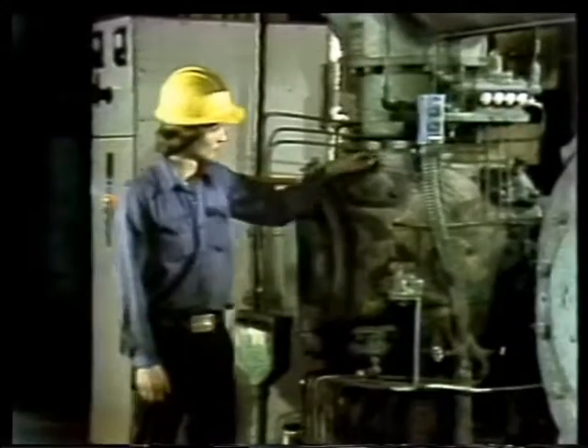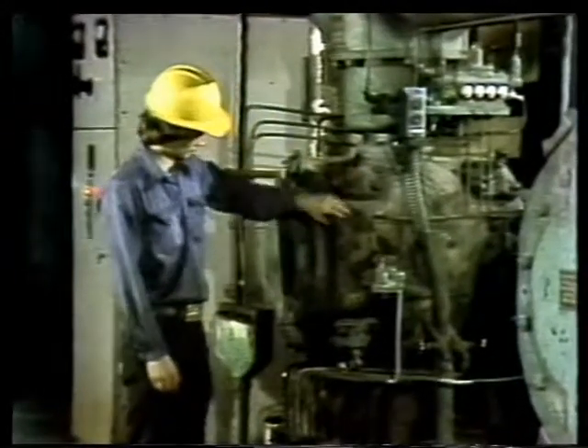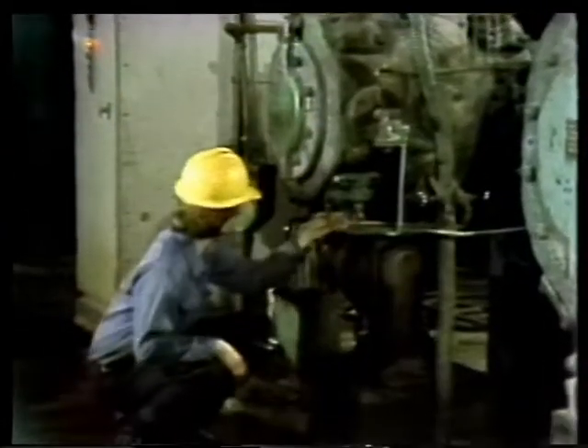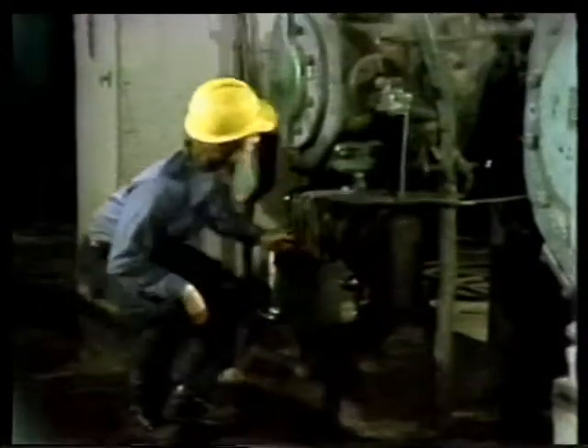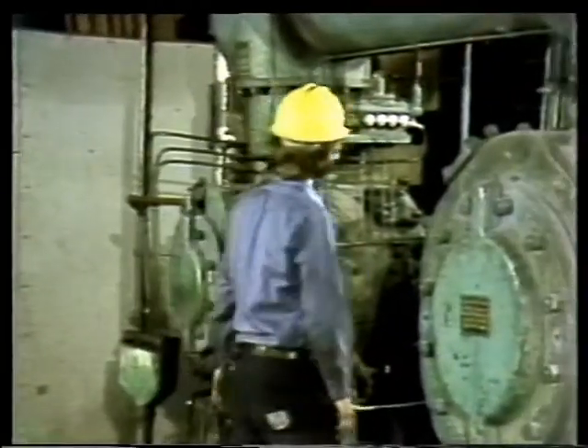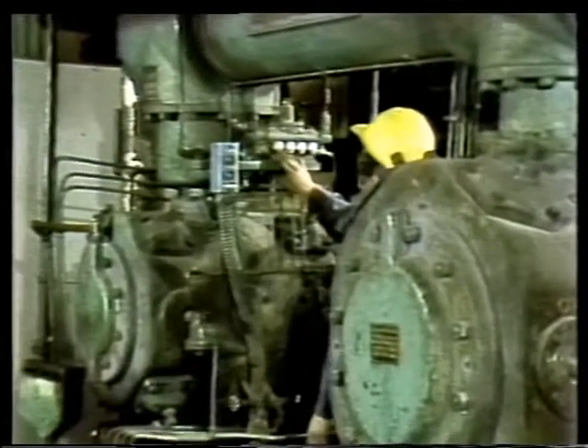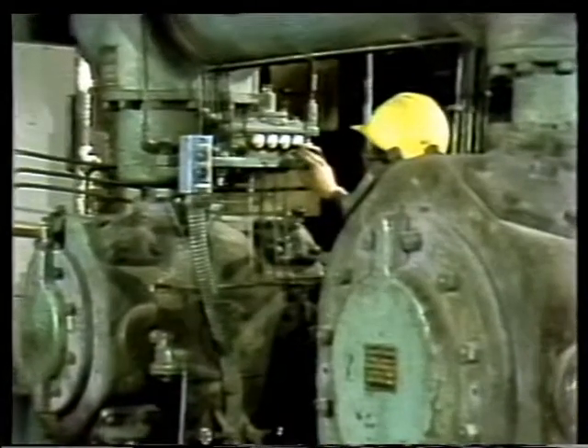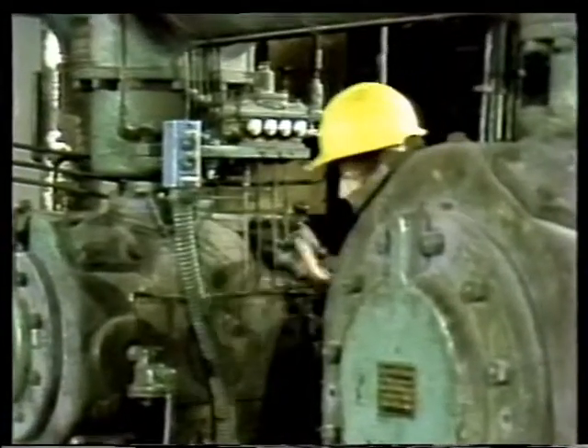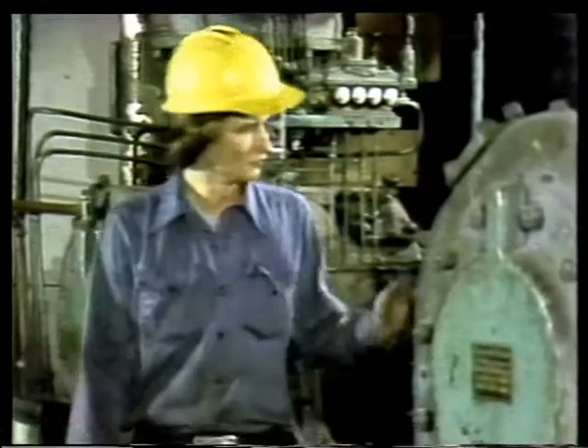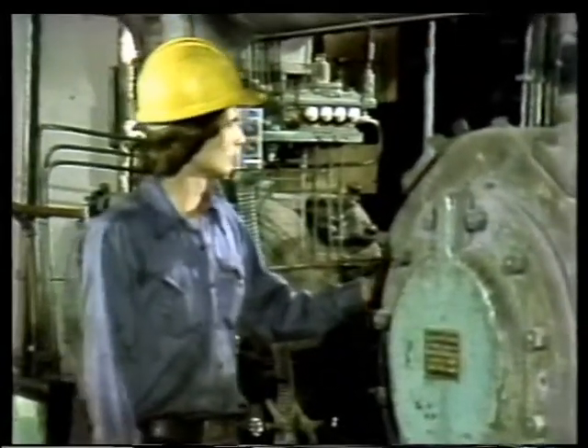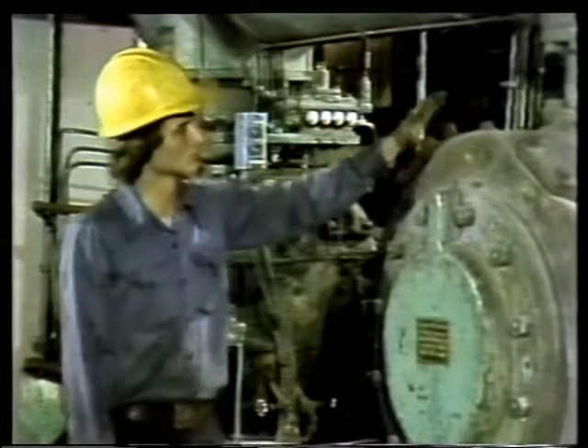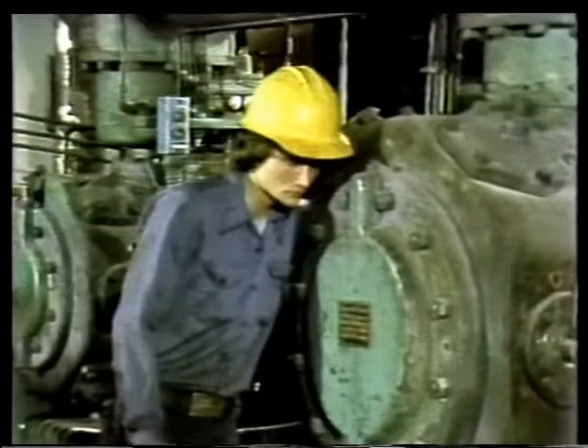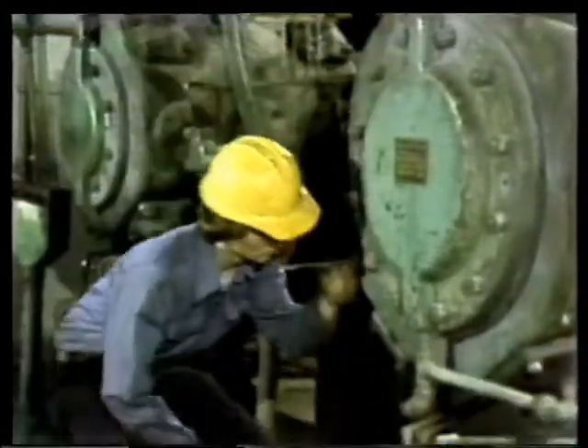After you've found out all you can, now you're ready to make your own inspection of the unit. If the compressor is operating, your inspection will include looking, listening, and feeling for any problems. You should look for any signs of leaking oil or water and check gauges and sight glasses for any unusual readings. You should listen for any sounds of air leaks and unusual noises like knocks. You should also feel the unit for excessive vibration, temperature variation, or hot spots, and for air, water, or oil leaks.